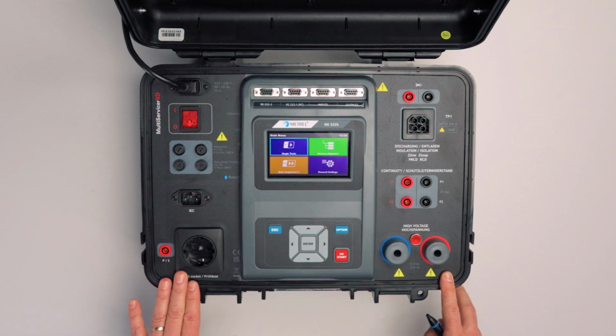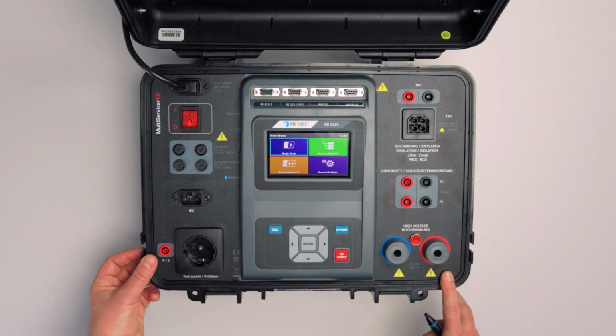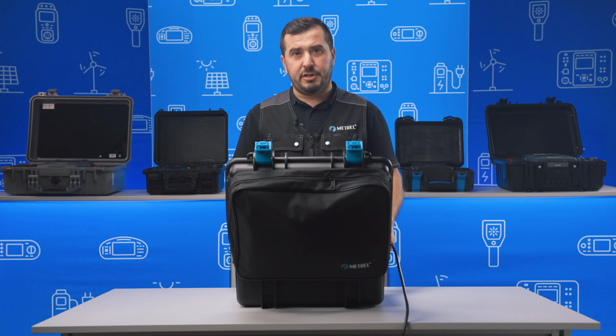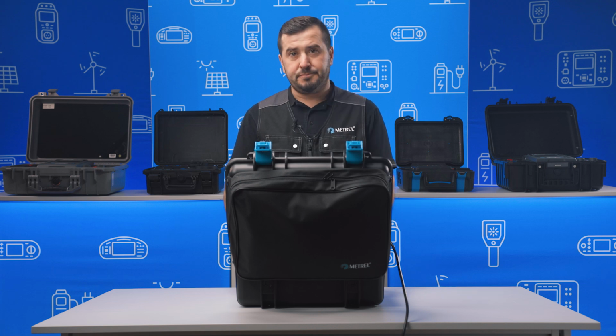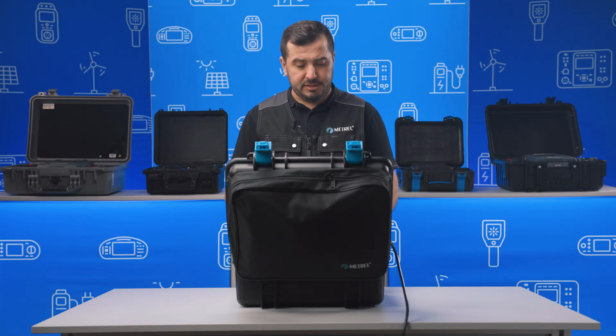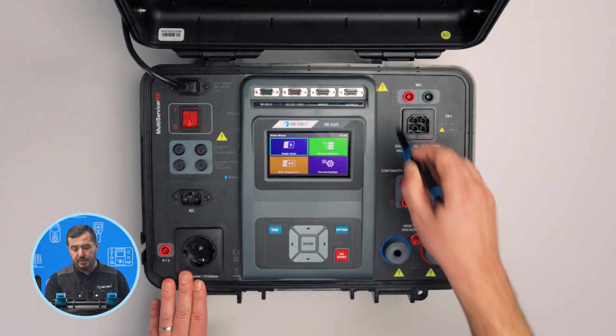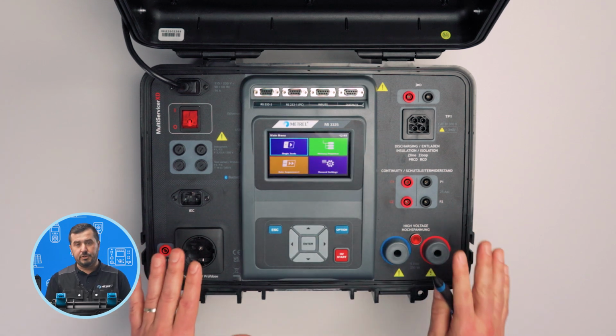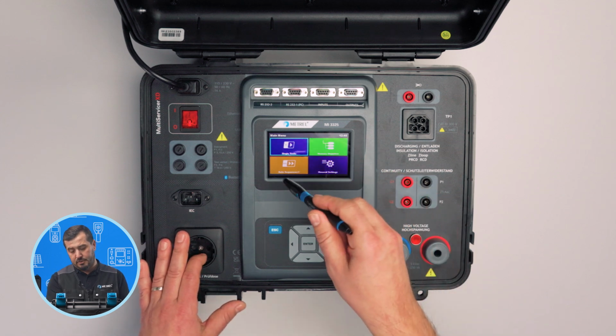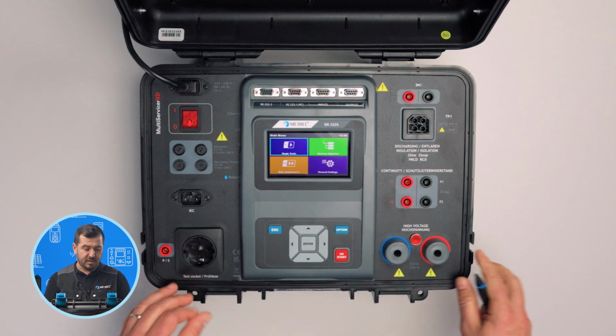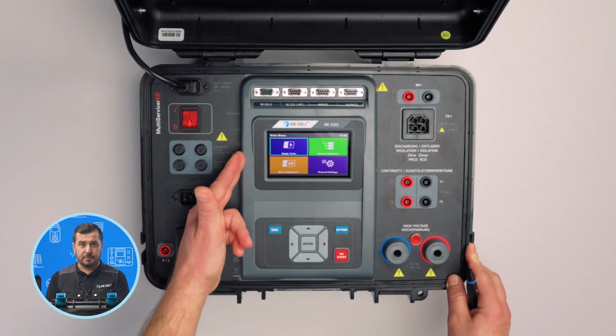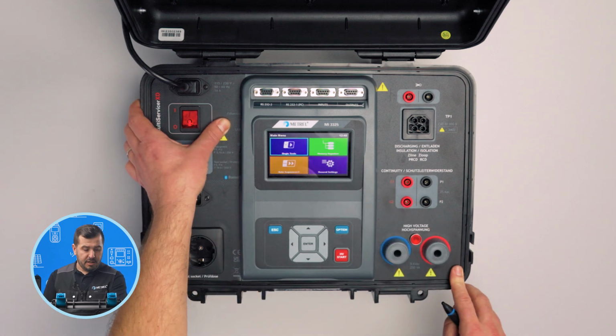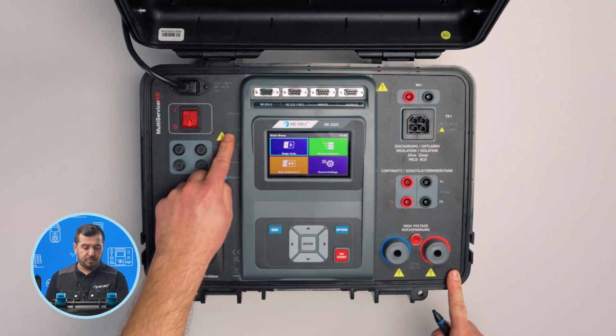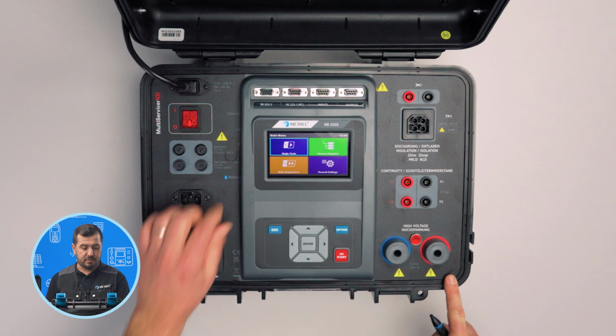Then, beside the instrument main test socket, there is a special test terminal dedicated for tests where the probe is needed. So, for example, earth continuity test with two-wire test method, or insulation resistance with a probe, so basically for class 2 devices. Then the main front panel, where the different communication ports, the touchscreen LCD and the keypad are located. On the left side of this main console we can find the Ethernet communication port, then the USB communication port and the location of the SD card.